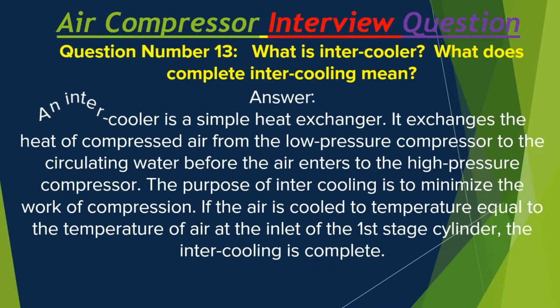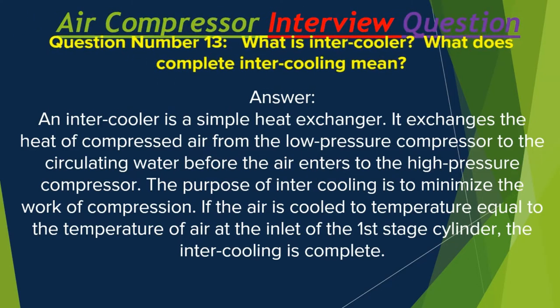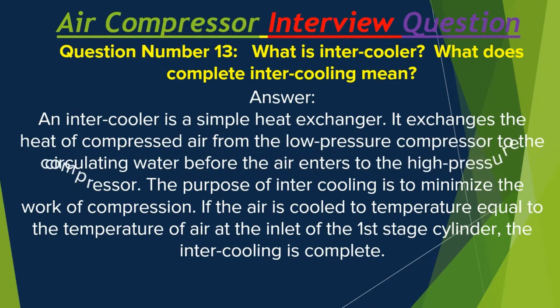Question number 13: What is an intercooler? What does complete intercooling mean? An intercooler is a simple heat exchanger. It exchanges the heat of compressed air from the low-pressure compressor to the circulating water before the air enters the high-pressure compressor. The purpose of intercooling is to minimize the work of compression. If the air is cooled to a temperature equal to the temperature of air at the inlet of the first-stage cylinder, the intercooling is complete.